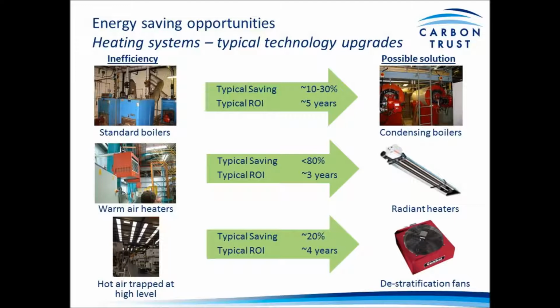The next recommendation is moving from warm air heaters to radiant heaters. Warm air heaters tend to heat the whole building. These are particularly applicable in large warehouse manufacturing type sites, when you potentially only need to heat a small area where you have occupants. With radiant heaters, you can get fast, efficient heat and often recoup your cost in less than a year on the right site. But you do need to have the right site.